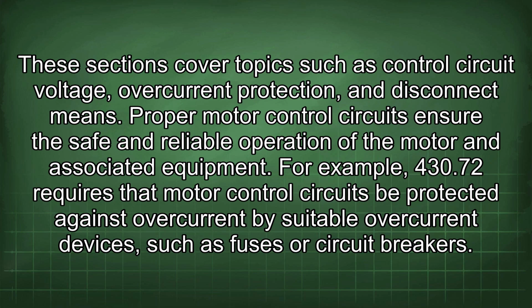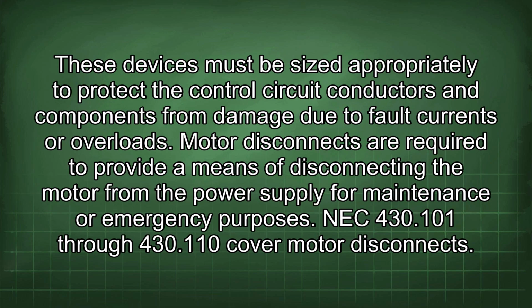For example, 430.72 requires that motor control circuits be protected against overcurrent by suitable overcurrent devices, such as fuses or circuit breakers. These devices must be sized appropriately to protect the control circuit conductors and components from damage due to fault currents or overloads.